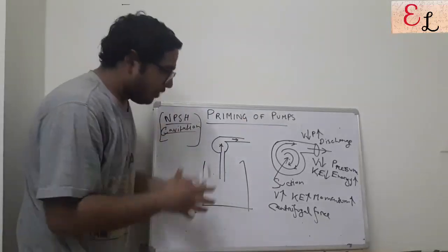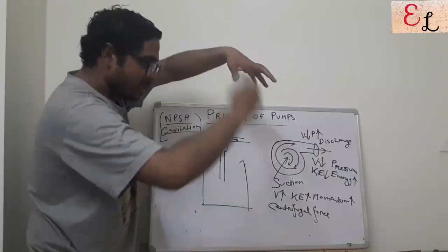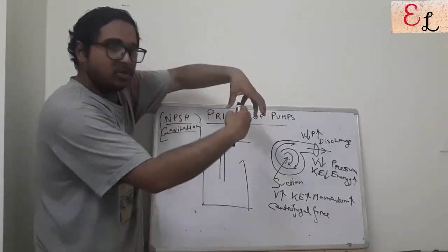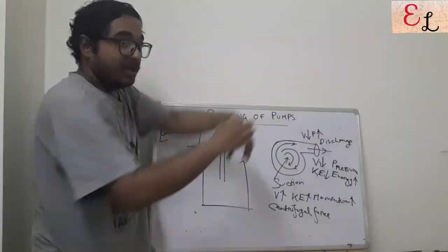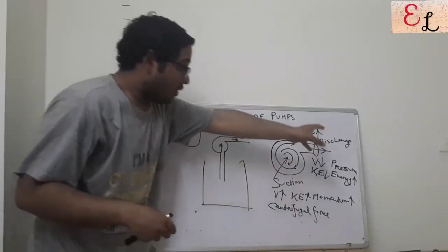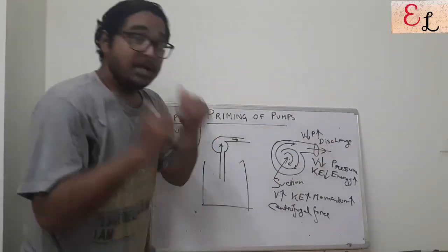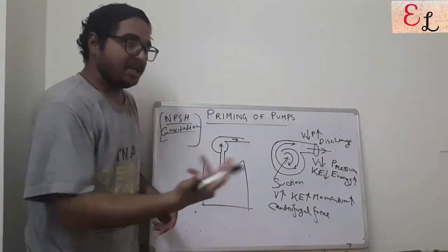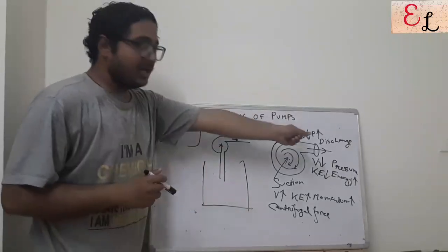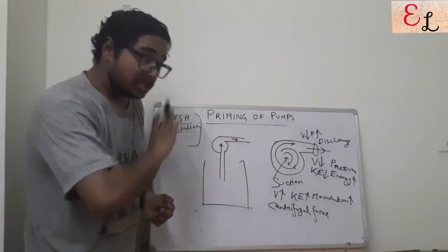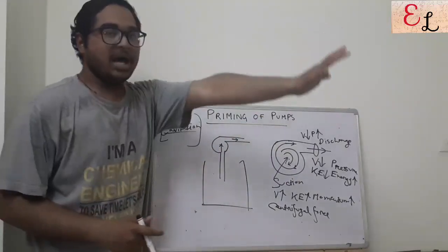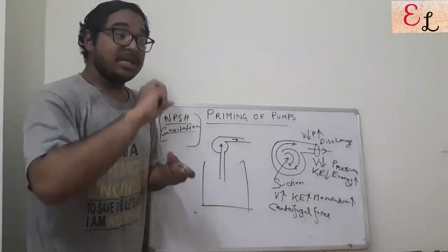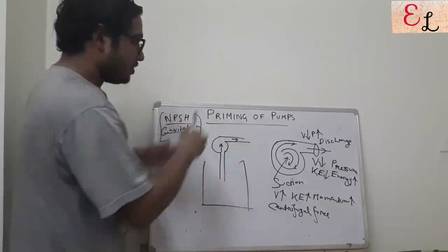So this is a simple explanation: the impeller rotates, creating a suction force. Liquid comes into the suction and is thrown to the periphery with a high amount of velocity and high kinetic energy. When it reaches the periphery the velocity decreases, kinetic energy decreases, and this is converted into pressure energy — the pressure head increases. So the discharge is at high pressure from low pressure. This is what the activity of a pump is, and this is how a centrifugal pump works.